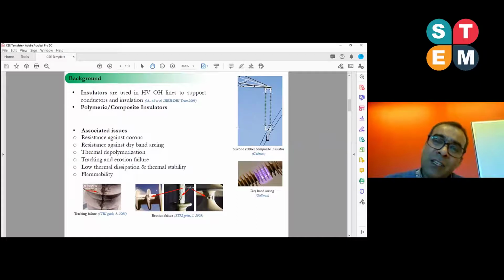There are several issues with polymeric insulators when they work in an outdoor atmosphere. One major problem is corona. Corona is a plasma, composed of electronic species and UV light, that can deteriorate the polymeric material. Another problem is that with the passage of service, pollution accumulates on the surface of the polymeric insulators.